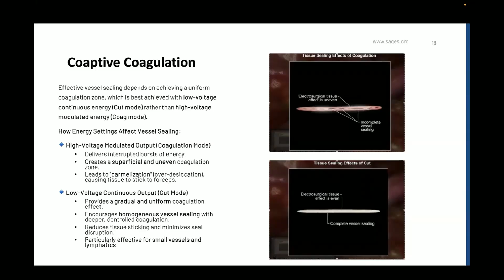So here we start with the oscilloscope. You can see that this is a coag mode, low duty cycle, multiple fires of current that can lead to uneven areas of tissue effect. Remember, these areas start to act like insulators, where the current can't pass through as easily because of the higher impedance in this tissue, versus using the cut mode while pressing the sides of the tissue together, which can lead to a more even spread and better hemostasis.